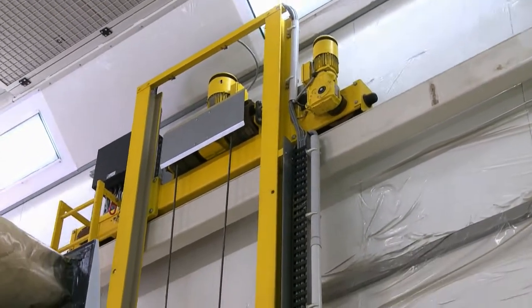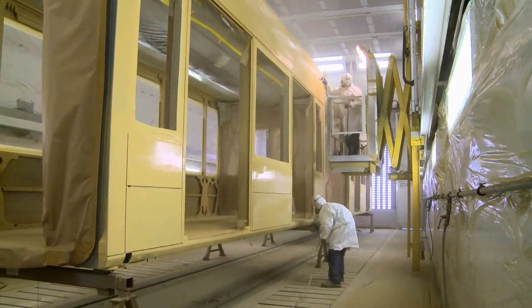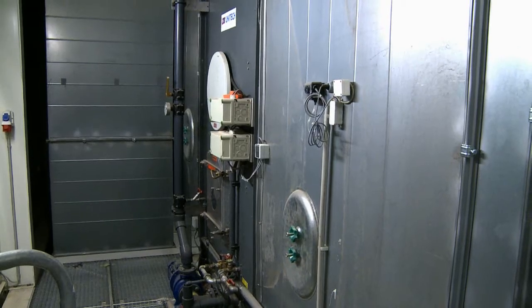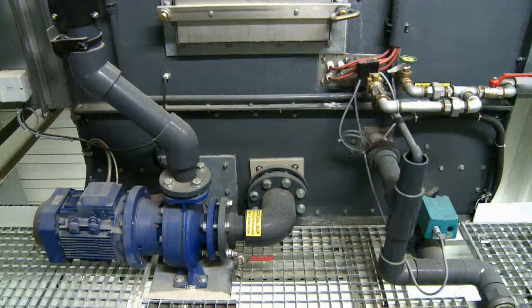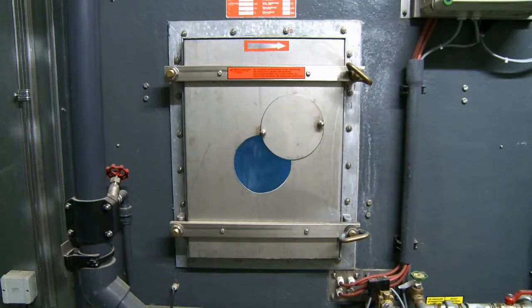The two coating technicians have first applied the filler and primer layers. Here in this cabin, only water-based coatings are used. In order to achieve good surface coverage, a preset humidity level must be maintained at all working temperatures. The machinery room therefore contains a humidifier which processes 50,000 cubic meters of incoming cabin air per hour, using normal city water from the municipal water supply. Because this closed-loop system handles a huge volume of air, the installation is also equipped with an ultraviolet sterilization system.